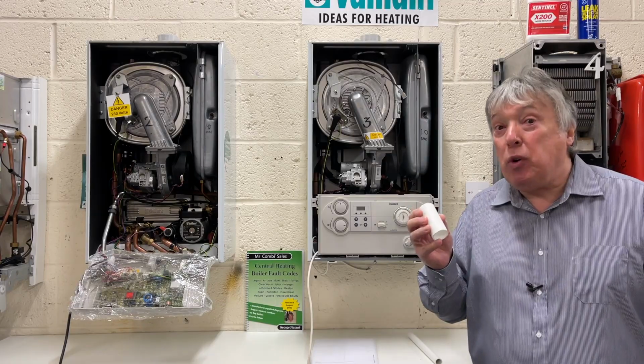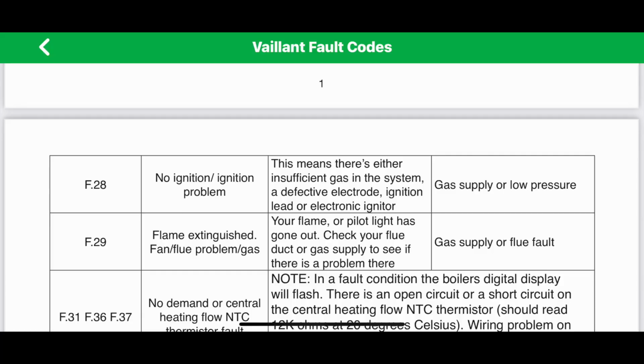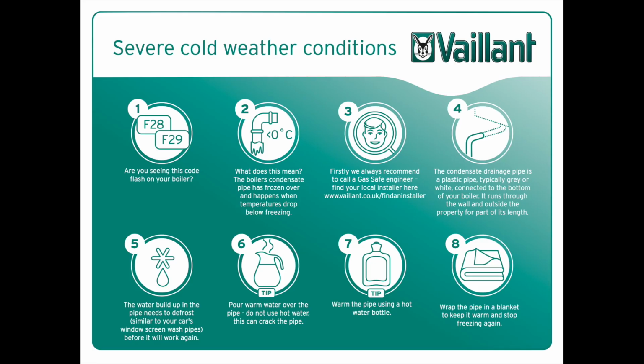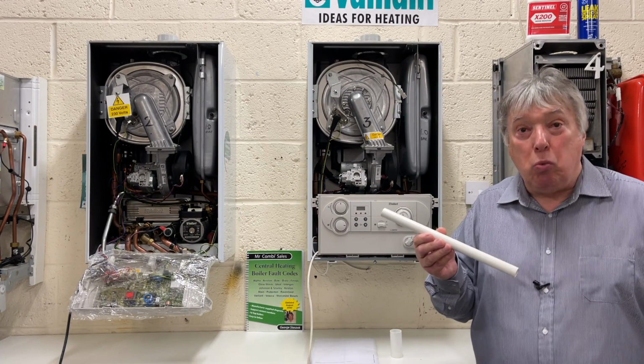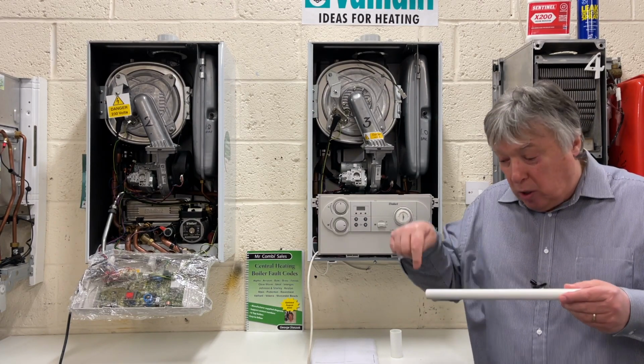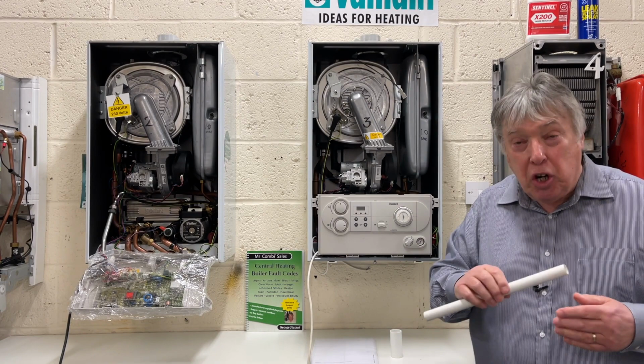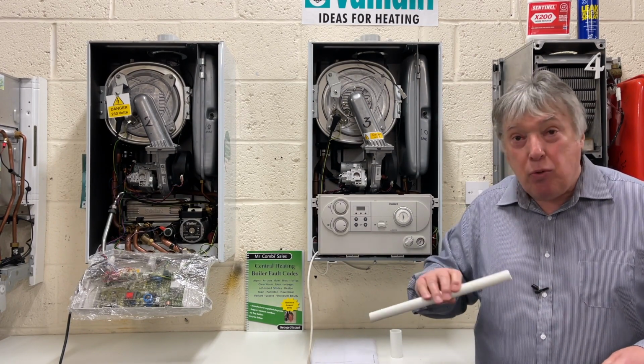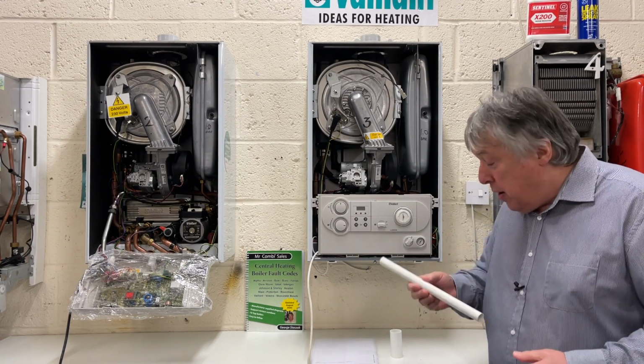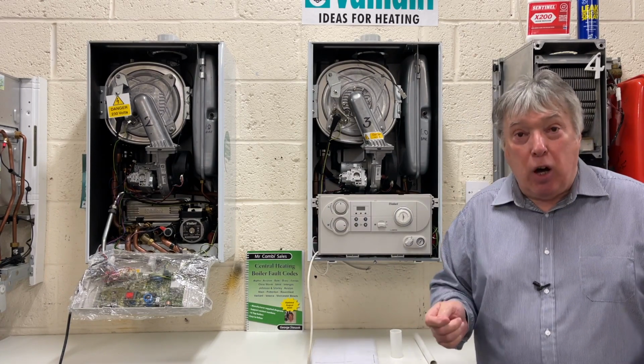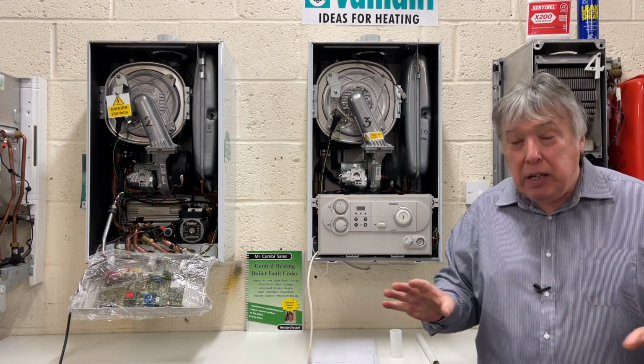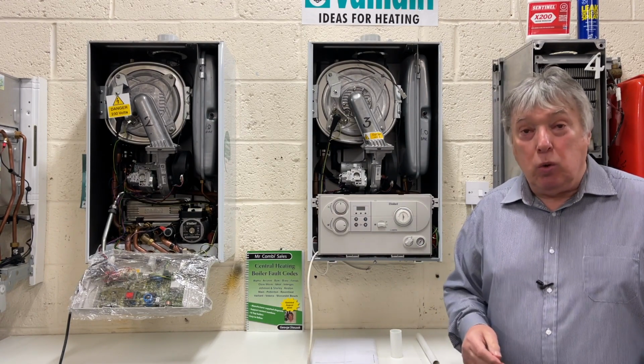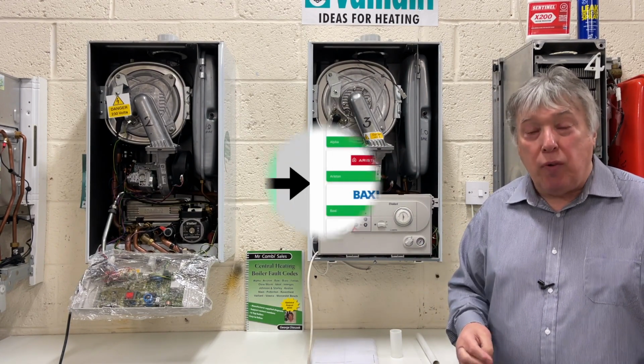But this is an F28 fault. So if you see that in the cold months, I would be looking at this. And if this is still installed, then you need to remove this and change it for the bigger size. Nowadays, in 2020, 2021, these pipes go down into the drainage in the house, so they don't go through the wall anymore. So look out for that. So remember, one F code can mean many completely different things, and I've given you the most popular two so far.